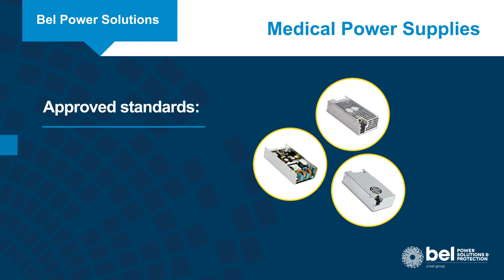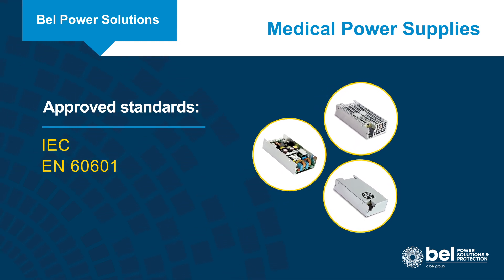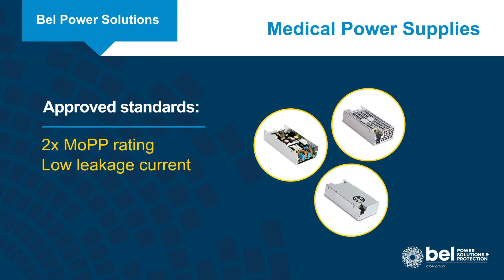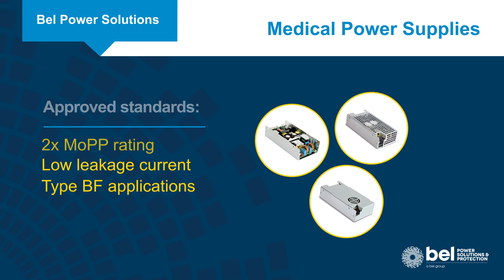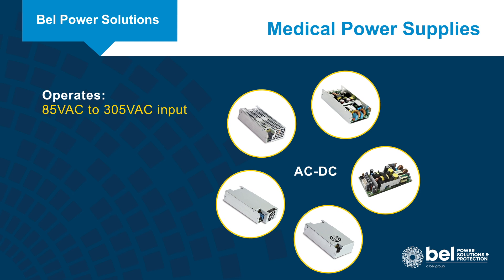The supplies are approved to the latest versions of the IEC and EN60601 standards for medical power supplies. They include a 2x MoPP rating, have low touch leakage current, and are suitable for type BF applications.